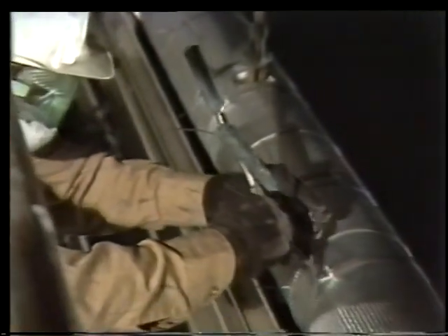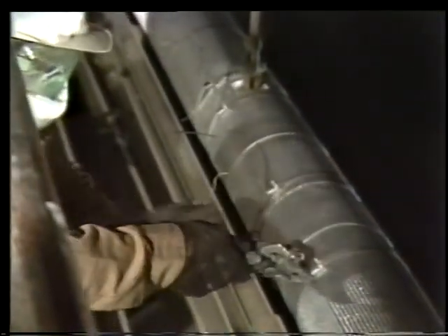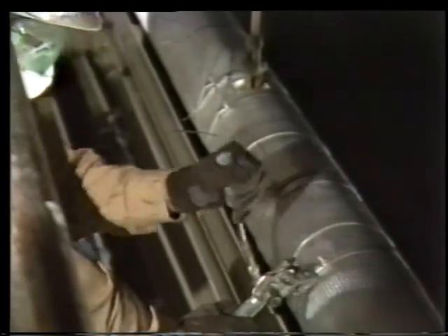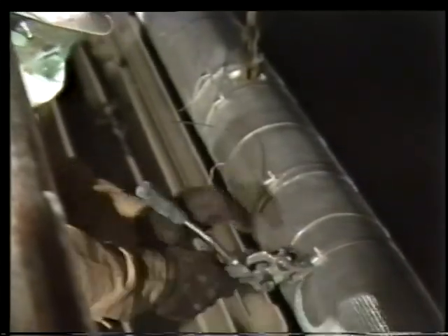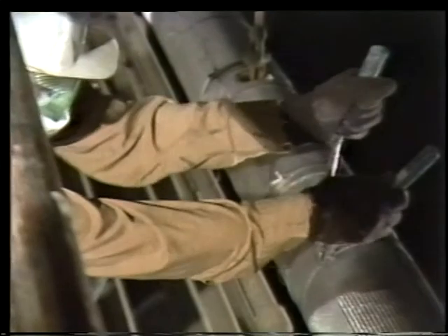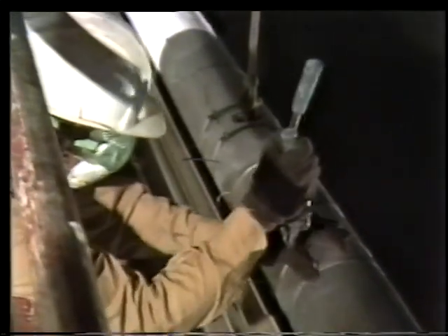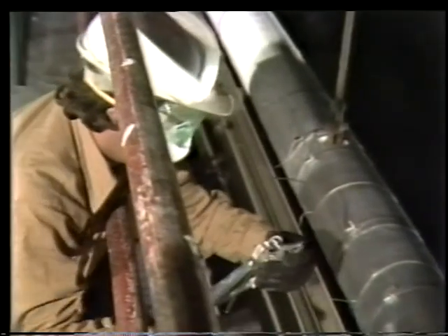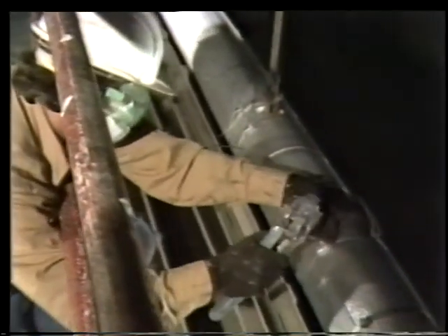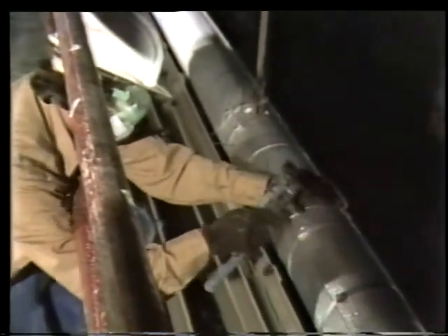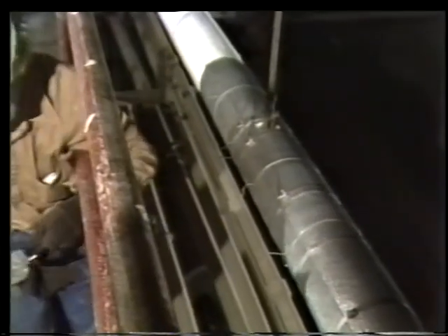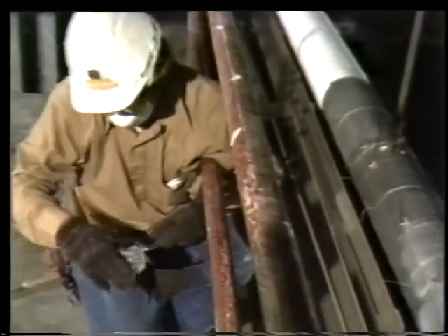This is a banding tool. Spreading the handles one way pulls the band tight. Pulling them in the opposite direction cuts off the free end of the band. The stub is bent over to keep it from pulling through, and it's held down by 2 tabs on the slot. Remove the piece of scrap from the banding tool and you're ready for another one.